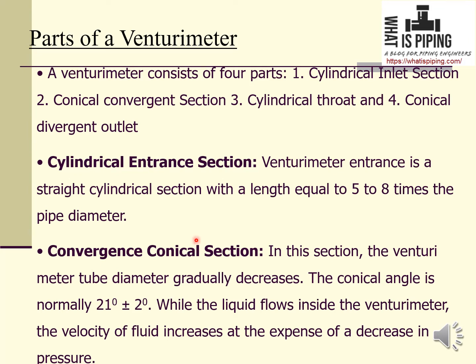The convergent conical section is where the venturimeter tube diameter gradually decreases. The conical angle is normally 21 degrees with a tolerance of plus or minus 2 degrees. As the liquid flows inside the venturimeter, the velocity of the fluid increases at the expense of a decrease in pressure.